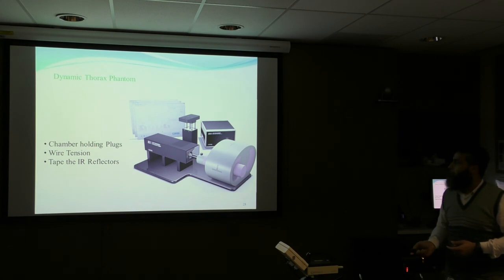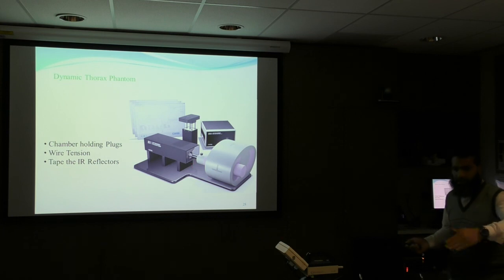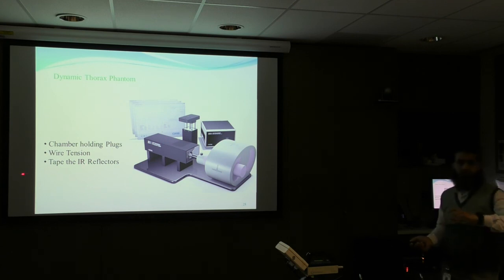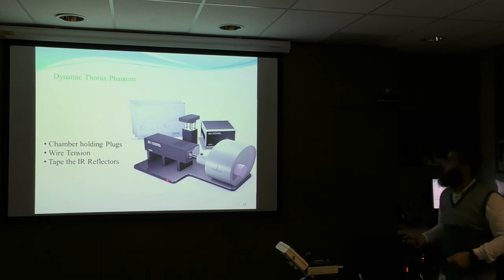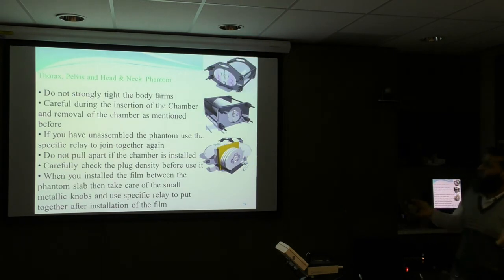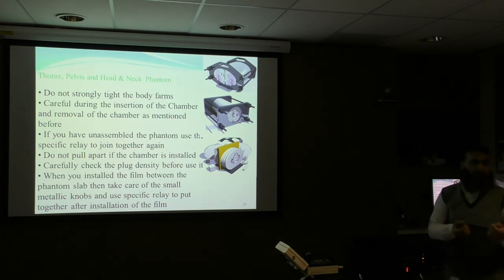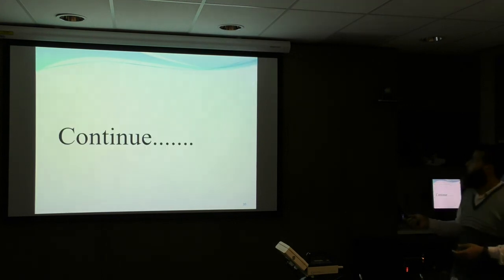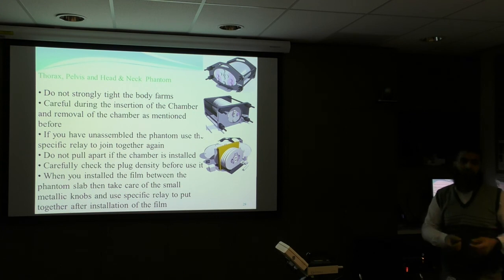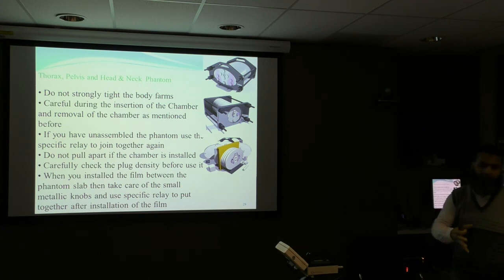Because this phantom actually travels in and out as well, when you put your chamber in, make sure that your chamber wire has sufficient flexibility to move in and out as it rotates - so the wire should have sufficient space and can't be stretched out. Do the body frames tightly, but these are made of plastic to be tissue equivalent, so try to make it tight but not too much - just enough to remain in a static position.